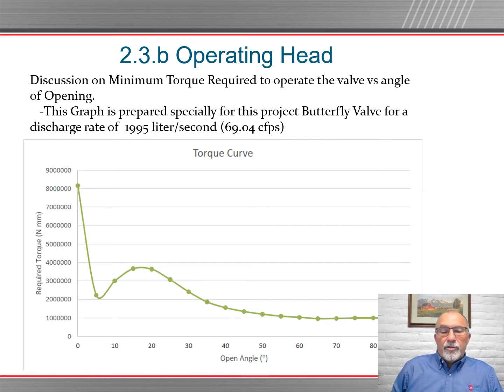It shows the increase in torque that is achieved to really get at the seat and how it breaks away, and it has a slight increase in torque curve and then slowly decelerates to the full 90-degree opening. And if you're closing it, it's the exact opposite. You can see at a full 90, it's relatively full flow, no resistance, and then it increases as you're closing it into a high resistance as it's seating itself, then it drops off as it is in the seating position until you get to a fully closed position.